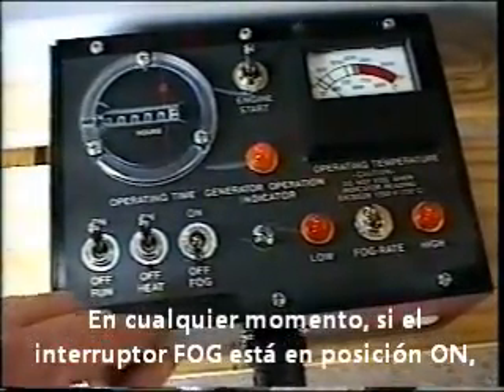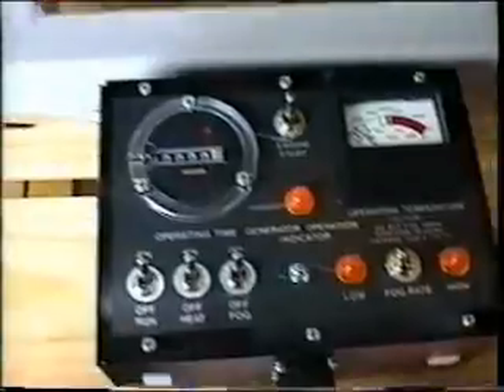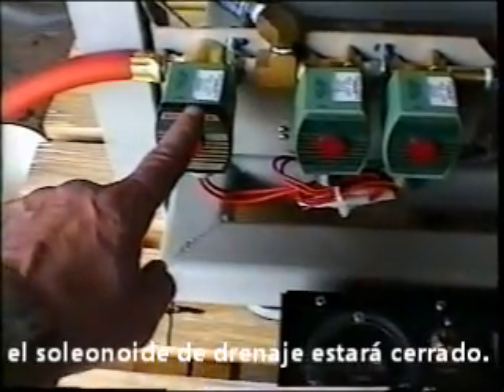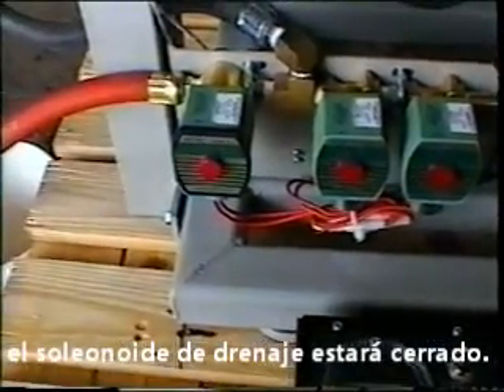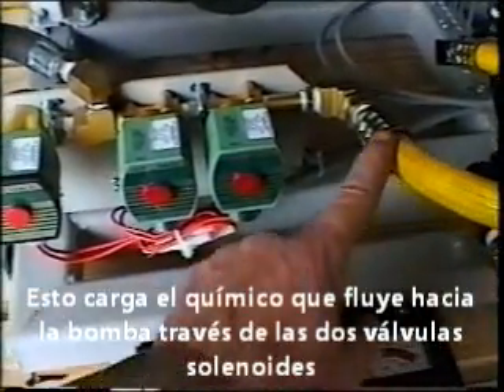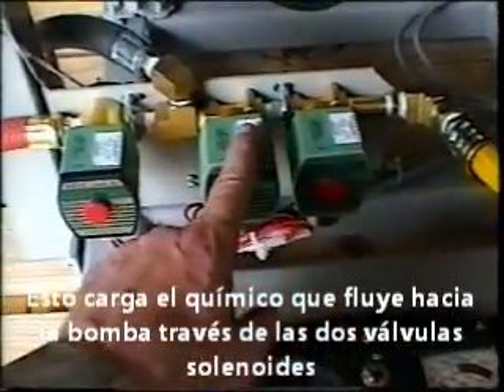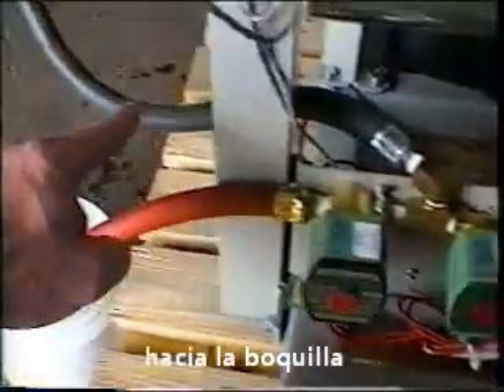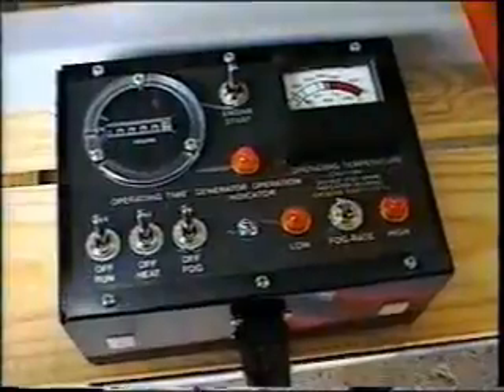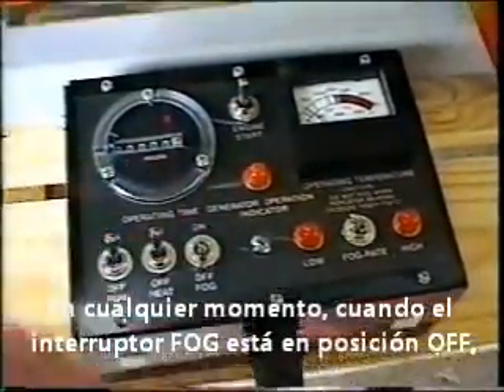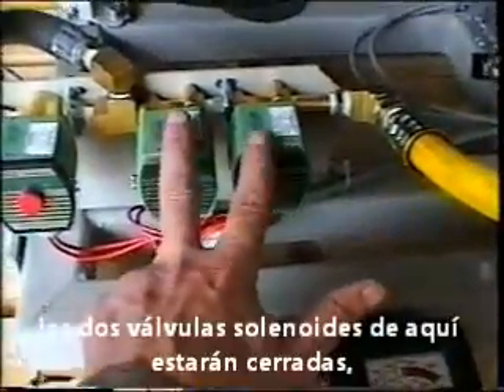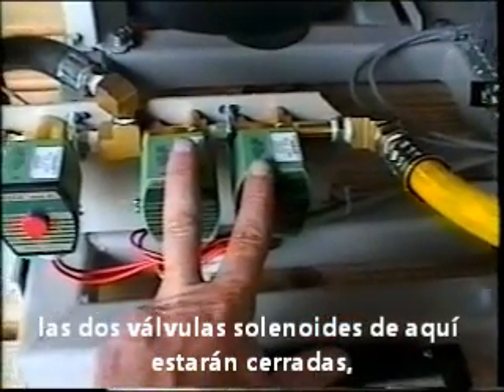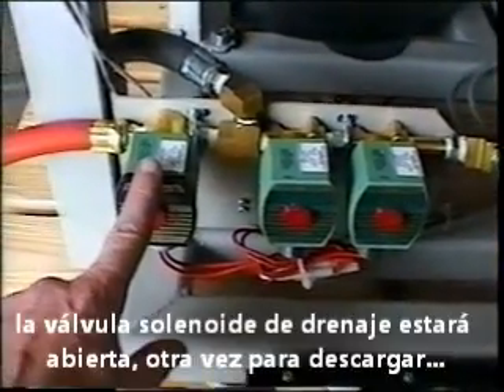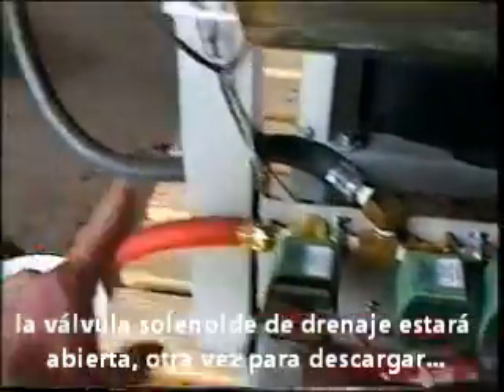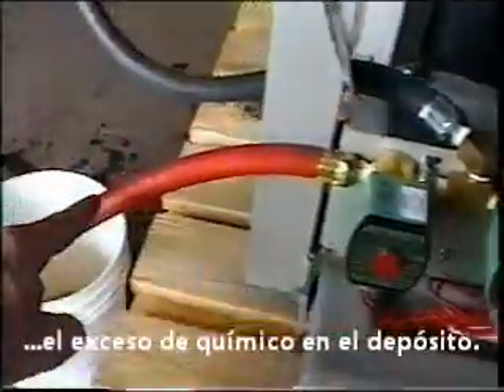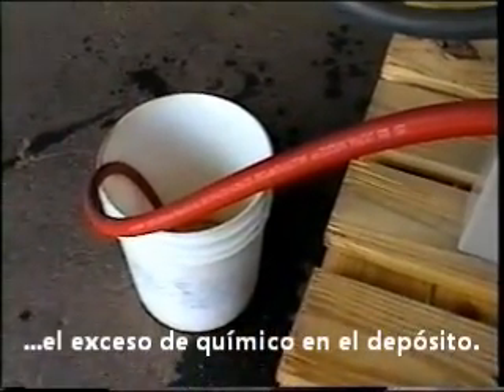Anytime that the fog switch is in the on position, the drain solenoid will be closed. This allows the chemical to flow from the pump through the 2 solenoid valves into the nozzle. Anytime that the fog switch is in the off position, the 2 solenoid valves here will close. The drain solenoid valve will open again to allow the overflow into the container.